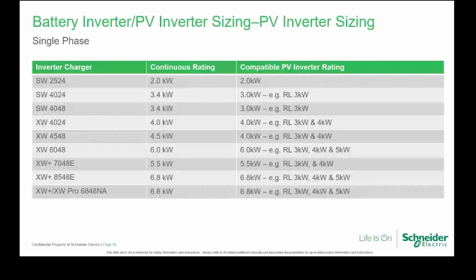So when we look at the inverter charger and some of the continuous ratings, and then look at the compatible PV inverter ratings, for example, these are legacy ones, the RL is just another example of the inverter. Obviously, there are inverter brands out there that are compatible with our system, like SMA or Fronius, but you need to confirm with them whether that will work. But if you look at the 2524, that's really only compatible with a 2 kilowatt inverter. The 4024 and the 4048 SW are only really compatible with a 3.4 kilowatt inverter. The 4024 is 4 kilowatts, 4548 is 5.5, 6048 is 6, 7048 is 5.5, 8548 is 6.8, and the XW Pro 6848 NA is 6.8.